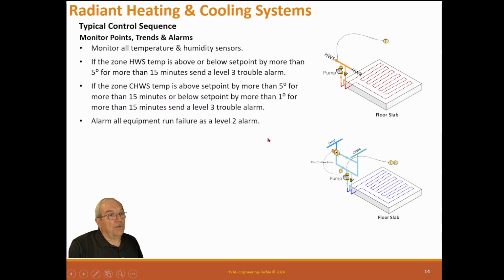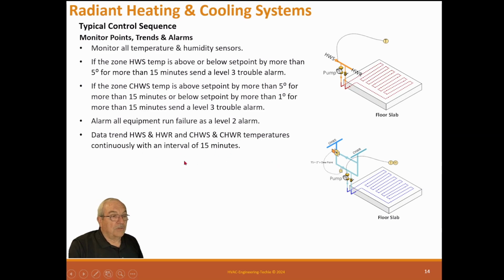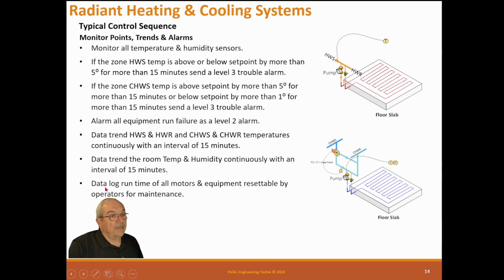Alarm all equipment run failures, level 2 alarm. Data trend the hot water supply and hot water return and chill water supply and chill water return temperature continuously with an interval of 15 minutes. Data trend the room temperature and humidity continuously with an interval of 15 minutes. Data log runtime of motors and equipment, resettable by the operators for maintenance. These are real simple systems, but they work really, really well.